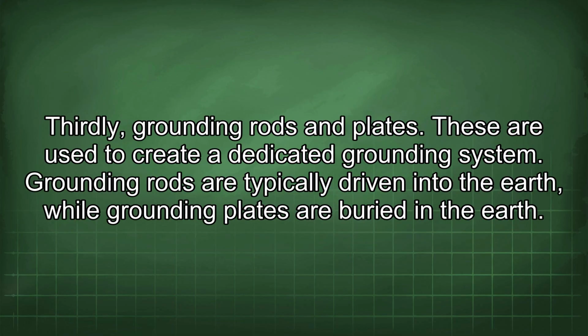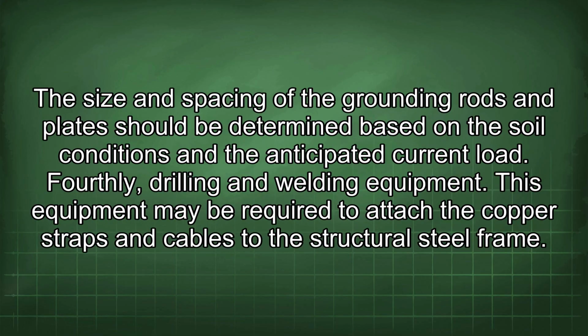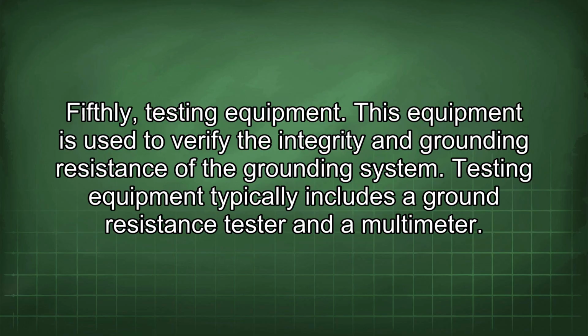Thirdly, grounding rods and plates. These are used to create a dedicated grounding system. Grounding rods are typically driven into the earth, while grounding plates are buried in the earth. The size and spacing of the grounding rods and plates should be determined based on the soil conditions and the anticipated current load. Fourthly, drilling and welding equipment. This equipment may be required to attach the copper straps and cables to the structural steel frame. Fifthly, testing equipment. This equipment is used to verify the integrity and grounding resistance of the grounding system. Testing equipment typically includes a ground resistance tester and a multimeter.